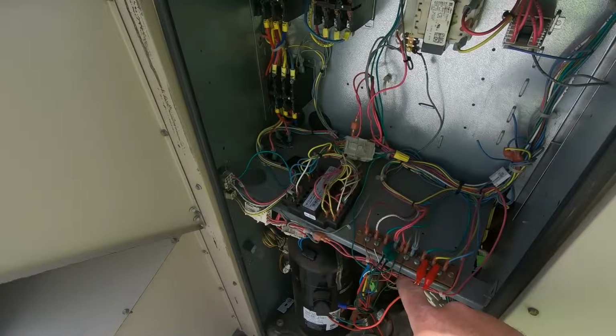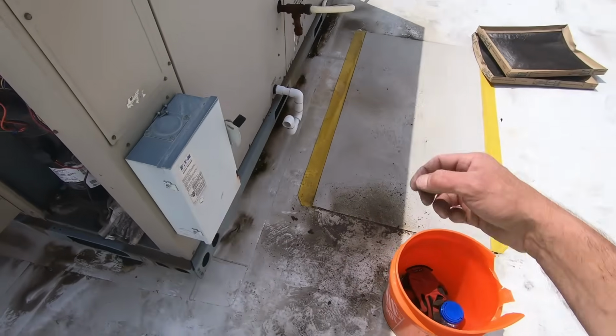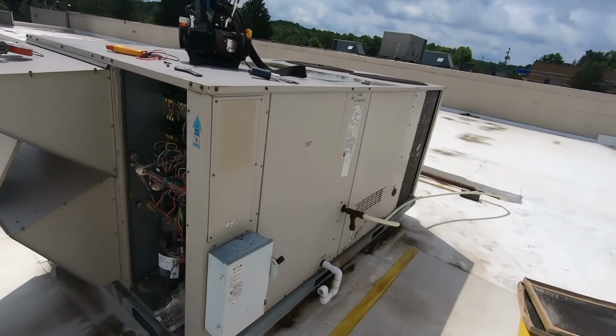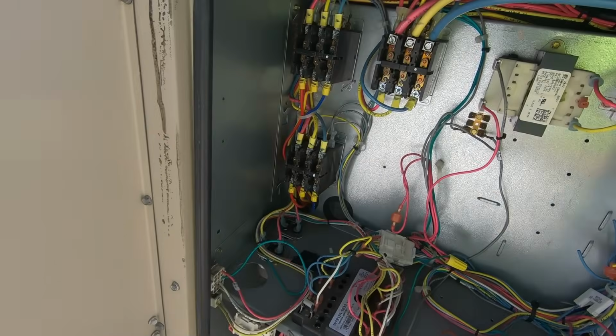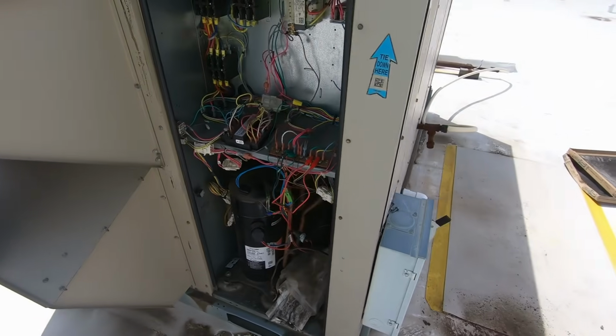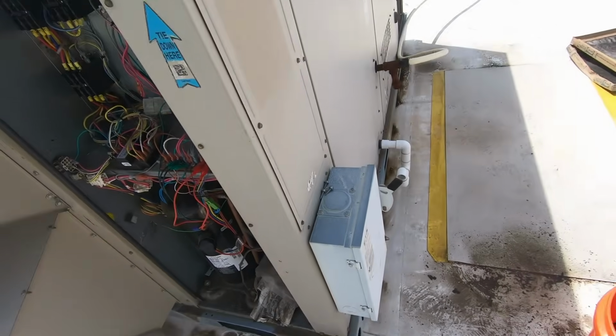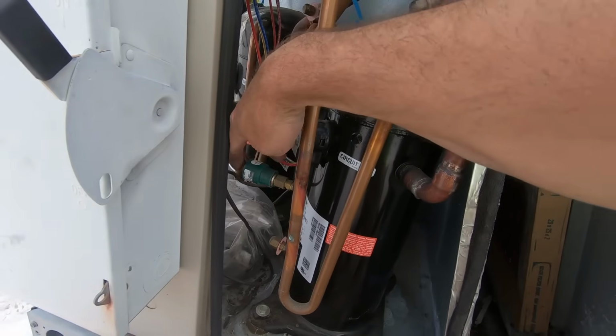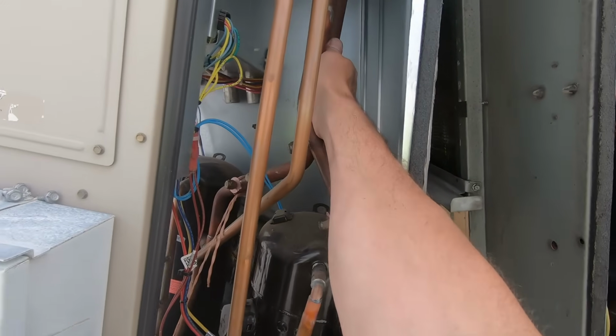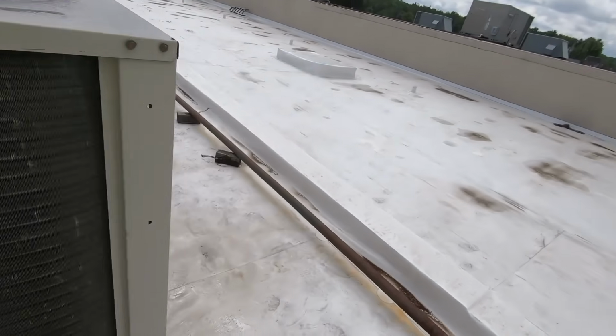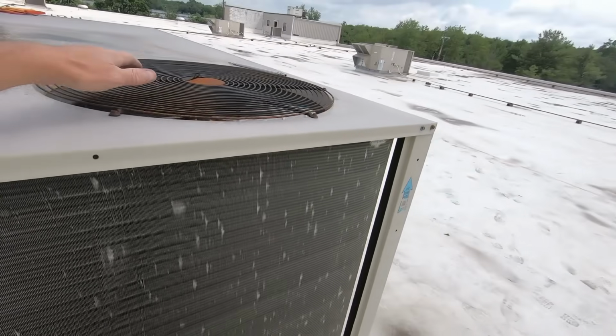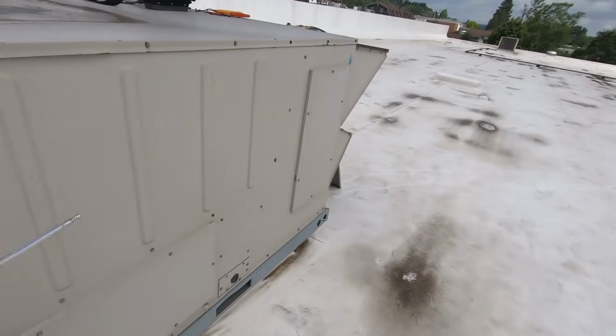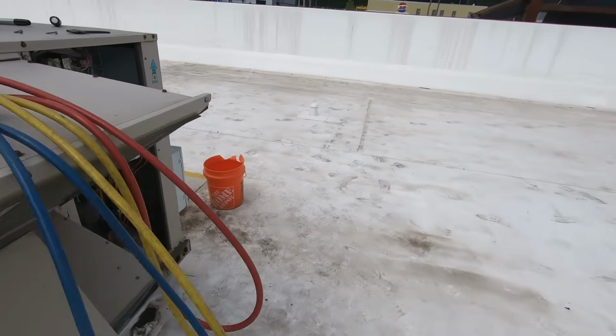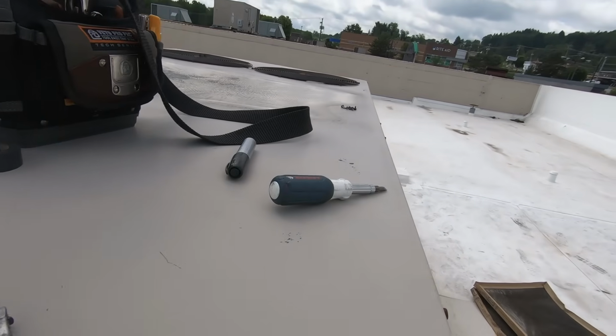I tested the economizer, it's good. Got Y1, Y2 jumped out. I got condenser fans. I don't have either compressor. High pressure switch was tripped. All right, so the high pressure switch was tripped on both. Is it a possibility it was running on a hot day and that switch got switched off? Both fans are running, blowers running, both compressors are running. Suction lines felt immediately cold as soon as I touched them.